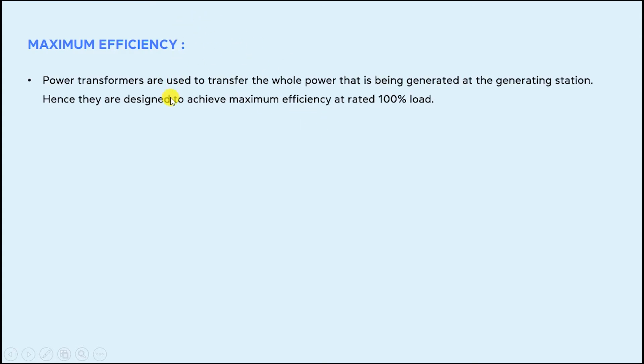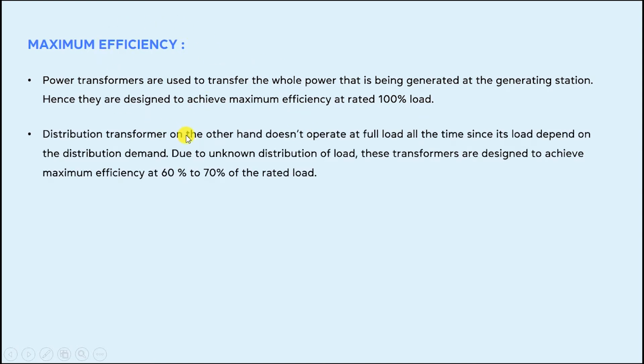One more basic difference is maximum efficiency. Power transformers are used to transfer the whole power generated at the generating stations, so they are designed to achieve maximum efficiency at 100% rated load. Distribution transformers, on the other hand, don't operate at full load all the time since their load depends on the distribution demand. These transformers are designed to achieve maximum efficiency at 60 to 70% of the rated load.